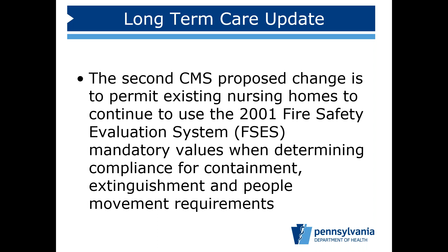CMS gave a 5-year extension for those types of facilities, but now what they're looking at, instead of the 5-year extension, is going back to the old 2001 FSES values. If they do that, a lot of these folks, as long as they're not a high-rise, would benefit - there is a limitation. If you're more than 7 stories, they would still make you use the newer FSES. But for buildings that had the old FSES that complied and met the 2001 edition, this would mean they can go back to those 2001 values and continue to comply, as long as you're 7 stories or less. It doesn't affect everybody, but for those it does affect, it's a huge change.